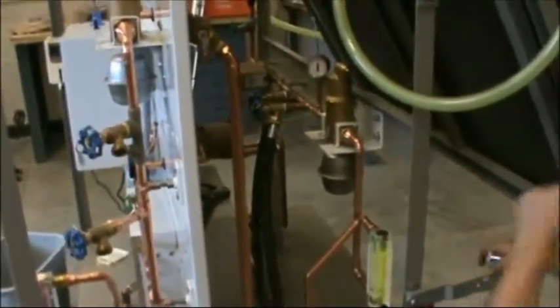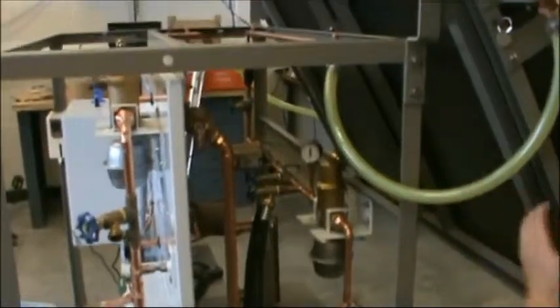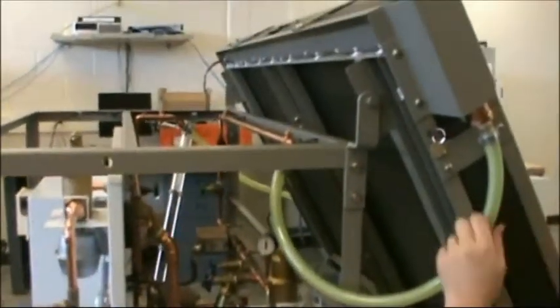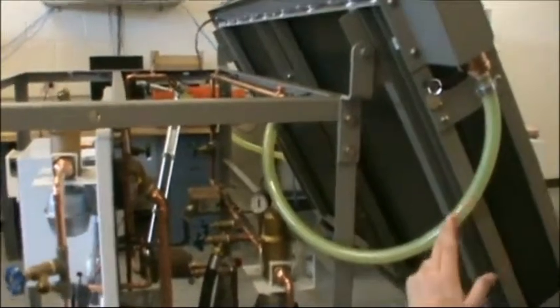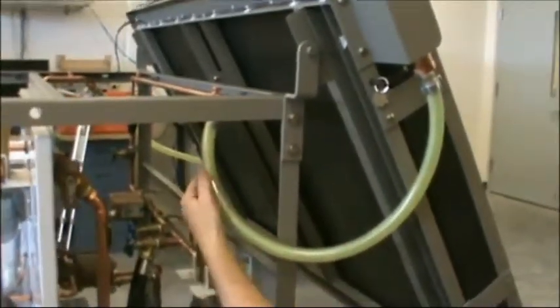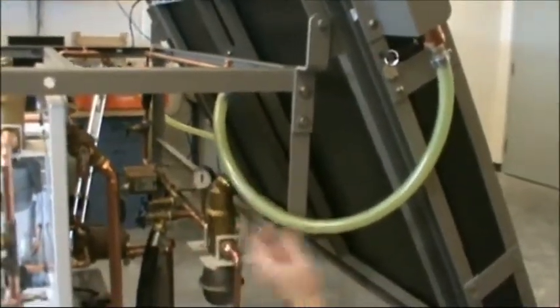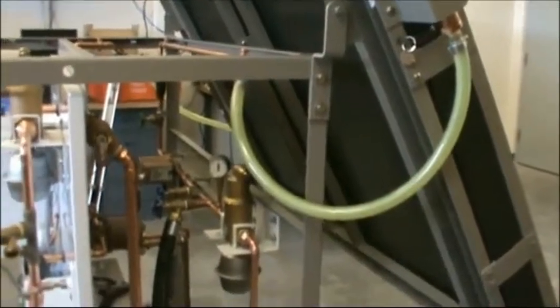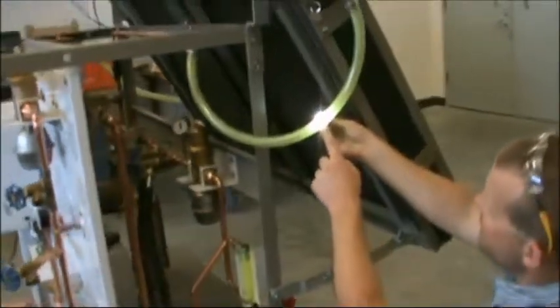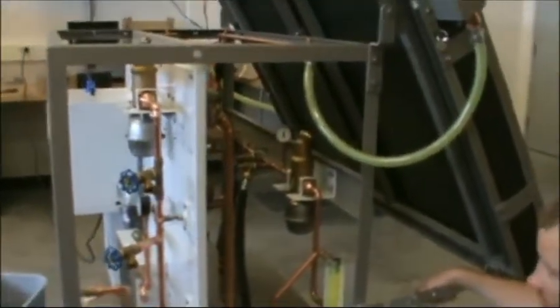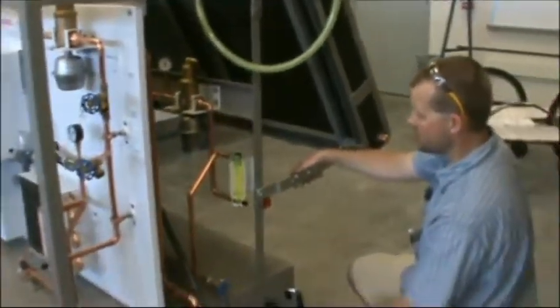This is the high temperature side, and again this is a training kit so we would not see a clear hose, but for demonstrations I can still see that I've got air and bubbles in the system. Now this is not uncommon. It's going to take a long time for this air to finally work its way out of the system.